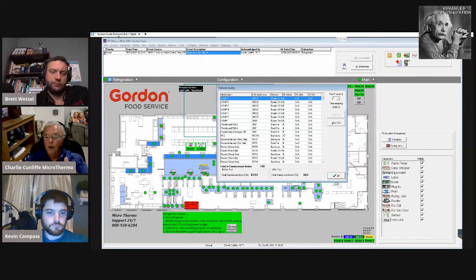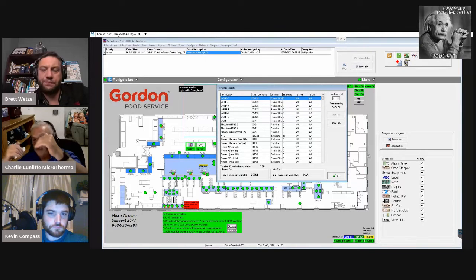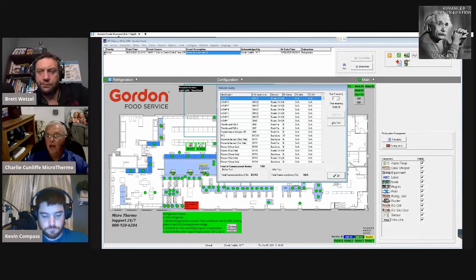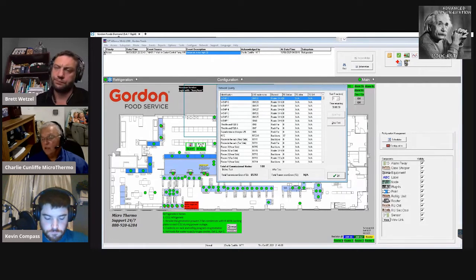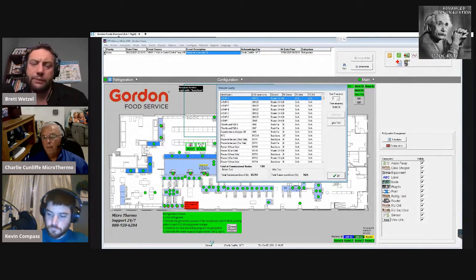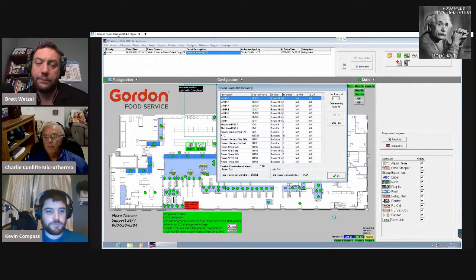Okay, so if you've done everything that I said, you tested the voltage, you've done the internal node test, you've looked at the recent error reports, you've done the physical tests on the relays, and you did a reset on the board, and you sent the configuration again, and the node still goes offline, then I would replace that node, Kev. All right, simple enough.